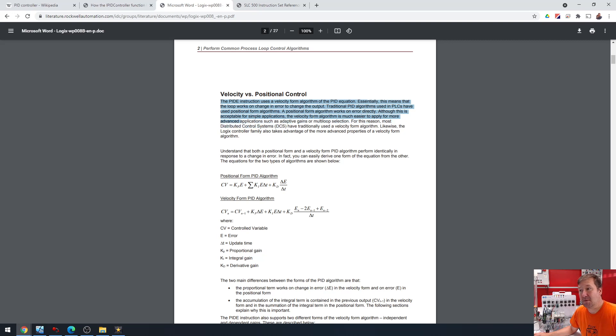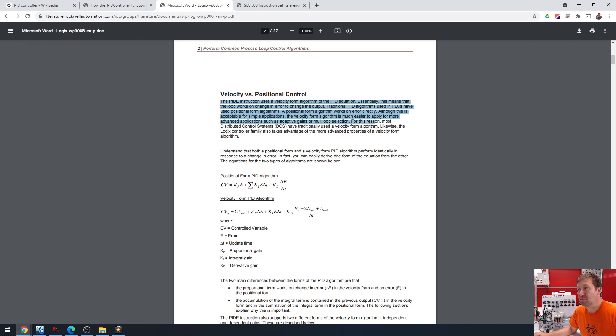Although this is acceptable for simple applications, the velocity form algorithm is much easier to apply for more advanced applications such as adaptive gains and multi-loop selection. For this reason, most DCSs have traditionally used velocity form algorithm.